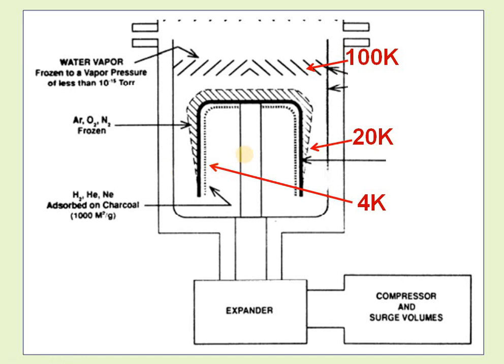A schematic of the cryogenic pump shows multiple panels: a 100 Kelvin panel, a 20 Kelvin panel, and inside, a 4 Kelvin panel. In the first stage at around 100 Kelvin, water vapor and hydrocarbons are deposited. In the second stage at 20 Kelvin, oxygen, nitrogen, and argon-like gases are deposited by entrainment. The temperature is then brought down further, and at 20 Kelvin, argon, oxygen, and nitrogen are deposited by the cryotrapping process.